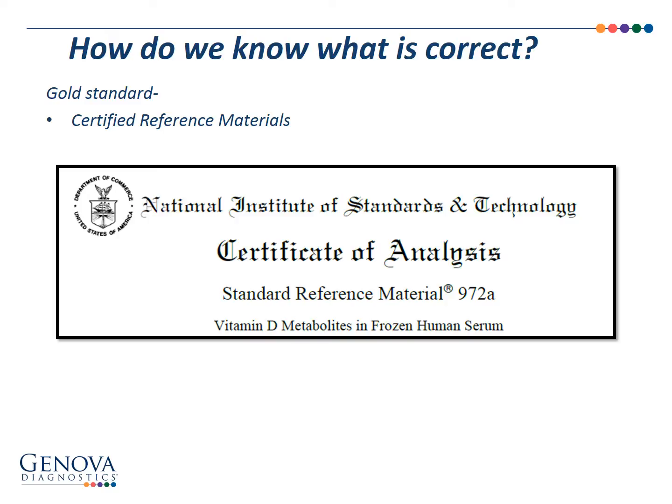And for a second source material, if possible, the gold standard is certified reference materials from the NIST, the National Institute of Standards and Technology. This is an internationally recognized body that creates stock solutions, and so we know that they're used all over the place, on all different platforms, by lots of different companies. So we have a high confidence in that value. They come with nice certificates of analysis, so you know exactly how much your target value is.